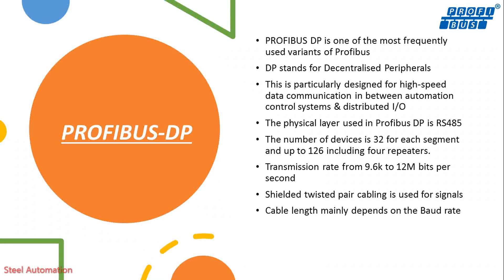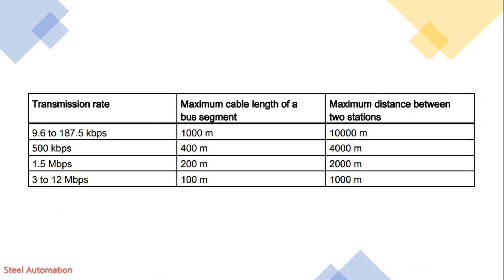Cable length mainly depends on the baud rate. For transmission rates from 9.6 kbps to 187.5 kbps, the maximum cable length of a bus segment is up to 1000 meters, whereas the maximum distance between two stations using an RS-485 repeater is up to 10,000 meters.